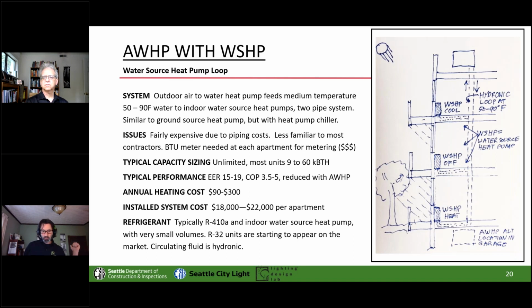So that same water source heat pump we were just talking about is actually an even better solution if you do an air to water heat pump or a heat pump chiller for water source heat pumps. We're saying you still have that compressor noise in your apartment. You still need a closet most of the time, although they can make ceiling mounted vertical or horizontal versions. But particularly for high-rise buildings, this has always been a viable option when you get beyond where you can push for VRF, which is a good many high-rise buildings. So if you're doing a high-rise tower, like the future is here. This is amazing. Your closet doesn't have to be on an external wall. It can sit far into the internal core with just an outside air opening. A lot of flexibility to these.